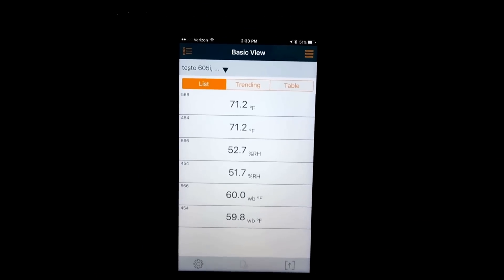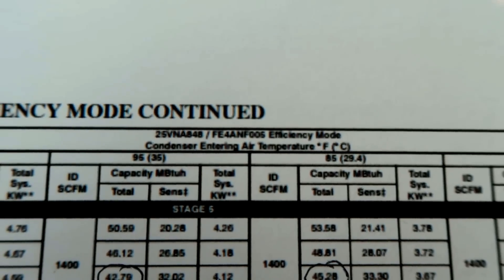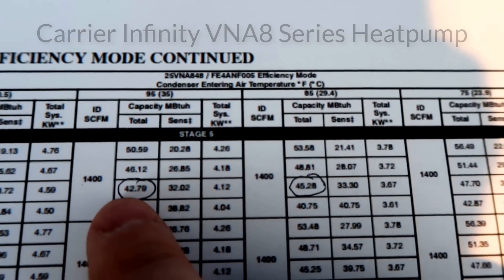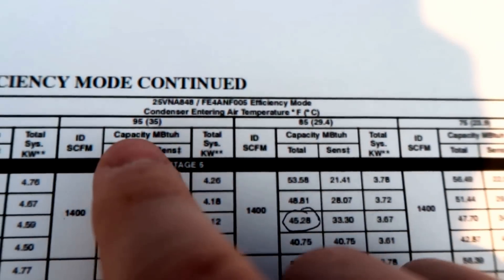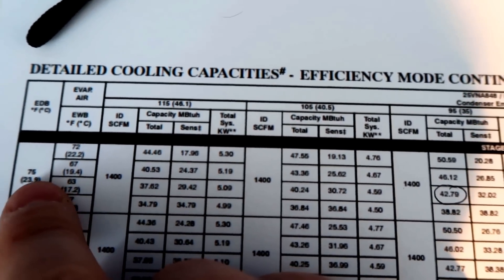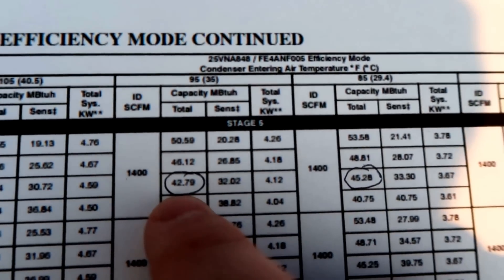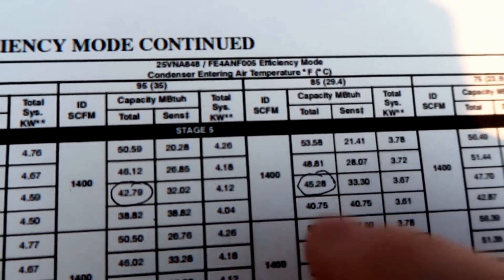Before we make our reading, we want to know what the system should be reading. I've gone ahead and pulled up my detailed cooling capacities for my particular system. My particular system is a 25 VNA 848 condenser with a FE4ANF005 air handler. I'm going to be in between two capacities because my outdoor temperature is between 85°F dry bulb and 95°F dry bulb. I'm at max stage — high stage — and my indoor temperature is close to 75°F dry bulb at about 63°F wet bulb. So we're looking for between 42,790 and 45,280 BTUs.